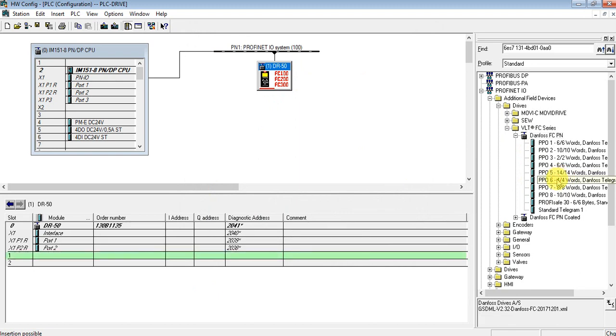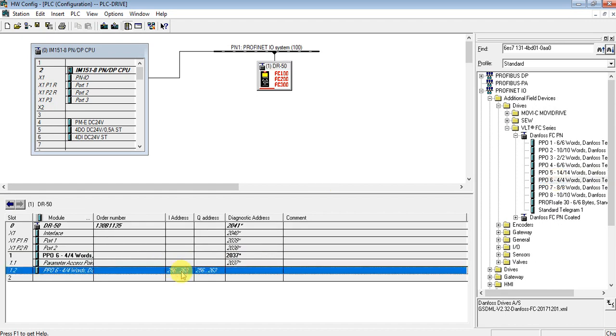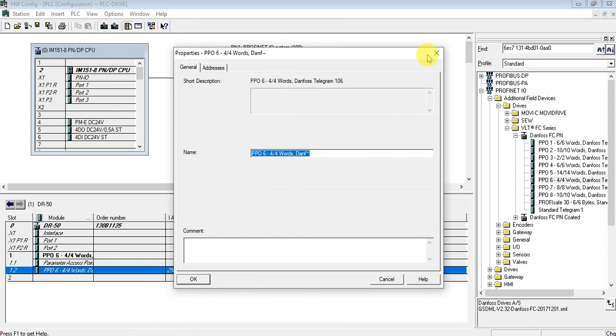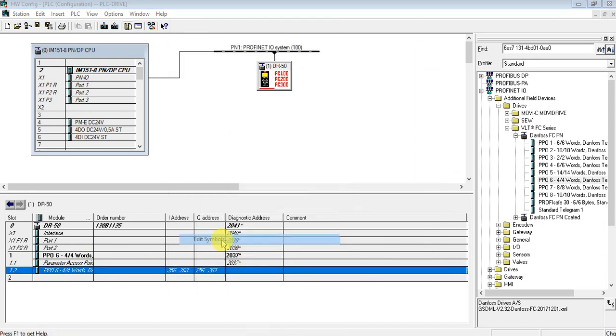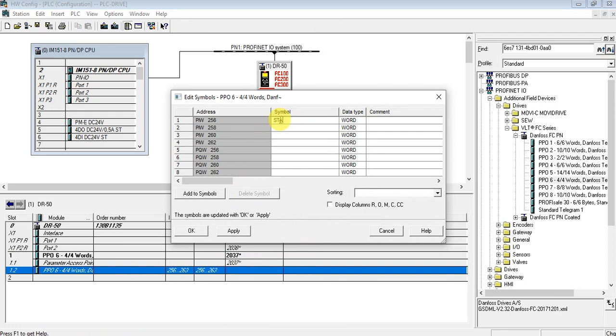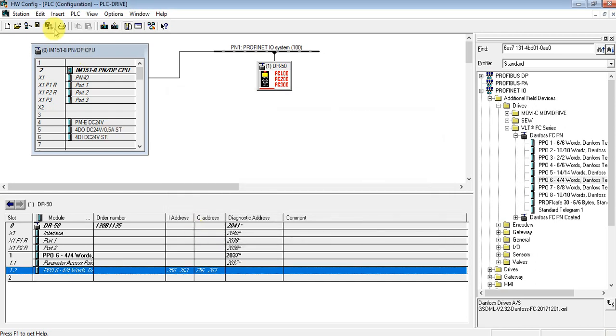Set the hostname to 'Drive 50' and change the IP address to 50. Now let's add the telegram used for communication between the PLC and the drive. Let's use telegram 6. The first word is the status word, the second is the actual speed of the drive. For writing, the first word is the control word and the second is the reference speed.